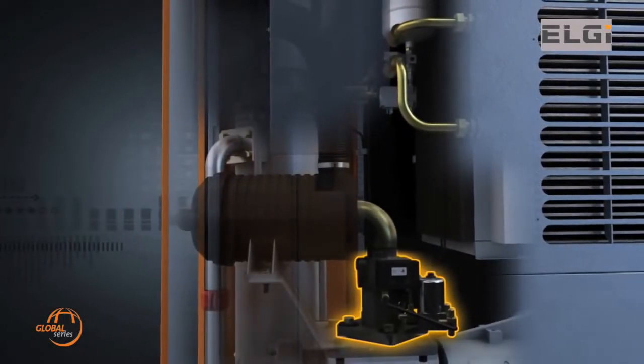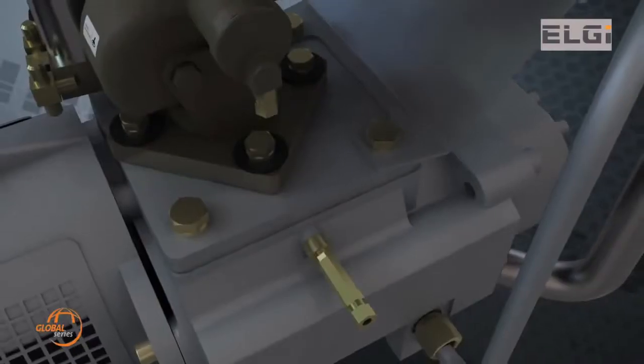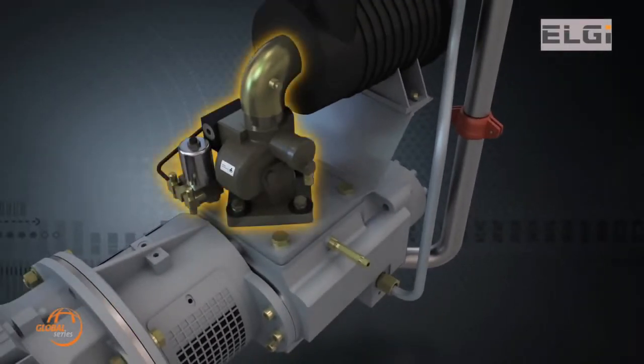A striking feature of the Global Series compressors is the new generation capacity control system integrated with a inlet valve installed at the compressor inlet. The intake valve reduces starting current and optimally controls the compressor capacity during less demand, thereby saving energy cost.